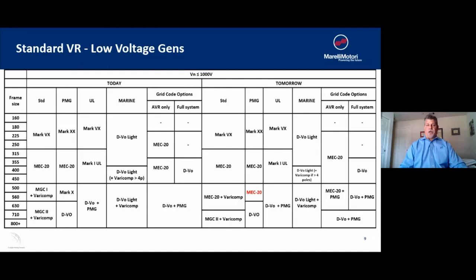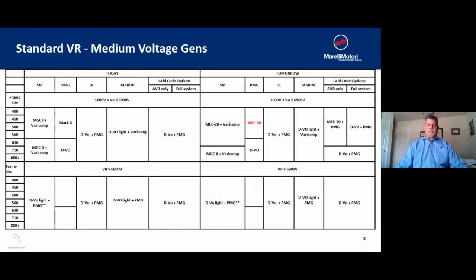Looking at medium and high voltage: Marelli's nomenclature for medium voltage is 1,000 volts to 6,900 volts. We call anything larger than 6,900 volts high voltage — it's still medium voltage class and still ANSI less than 15 kV, but that's just how we designate it. For medium voltage, we use the MGC1 and MGC2 as standard. For anything larger than 6,900 volts, we immediately go to our digital voltage regulator. For UL or Marine Society approved applications, we go full digital with our DVO or DVO Light product.